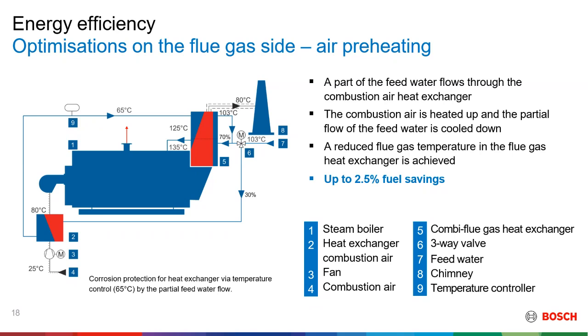Just a point to note that the assumption here is the water that is leaving the water service module is leaving from a full deaeration plant. That's why the temperature at entry is 103. Around 30% will flow into the air preheater. So in the air preheater, we have ambient air flowing in at around 20-25 degrees and leaving the air preheater into the burner at around 80 degrees. Then the water will recirculate back into the economizer and mix together with the water that is flowing directly from the pumps into the economizer, which is around 70%. And here the water again will be heated up with the economizer up to around 135 into the boiler.